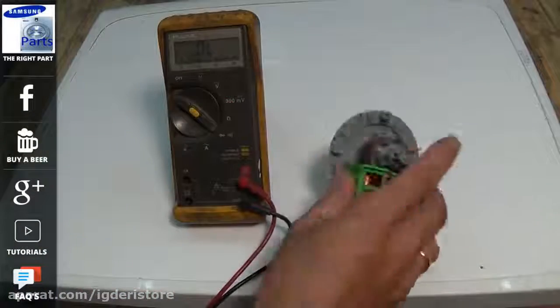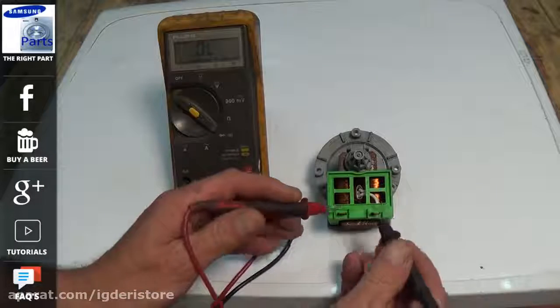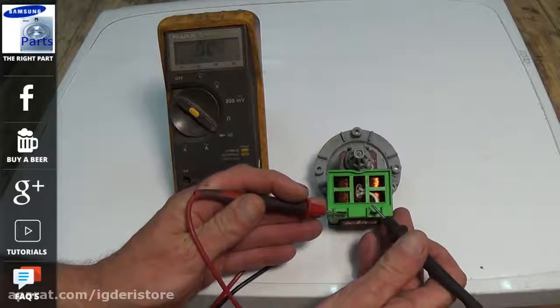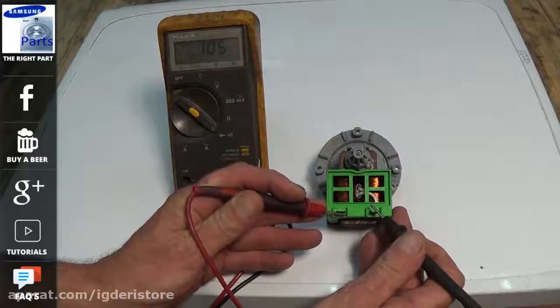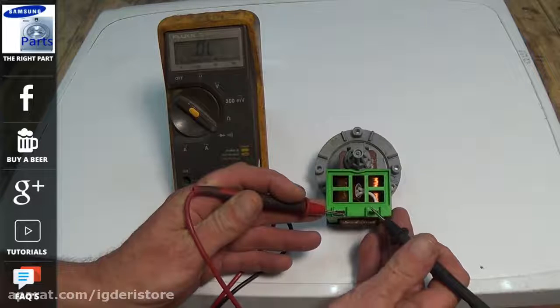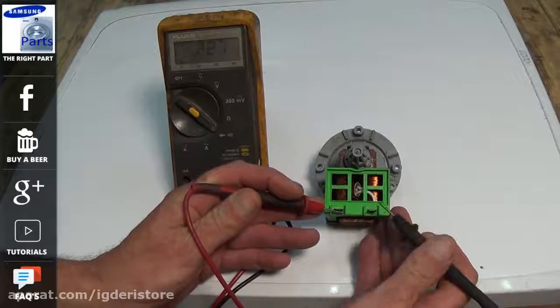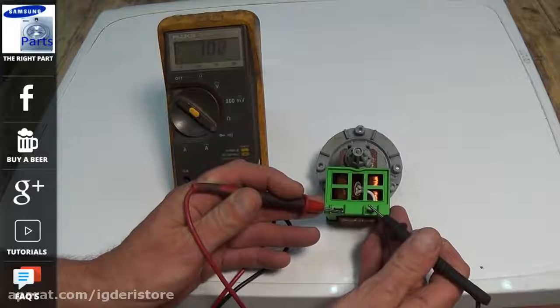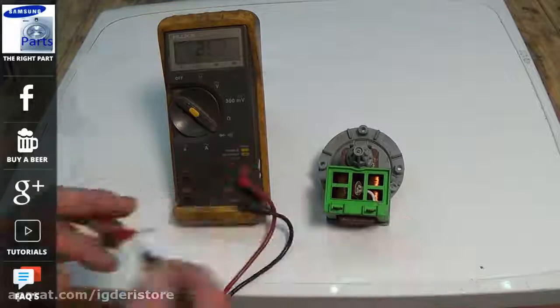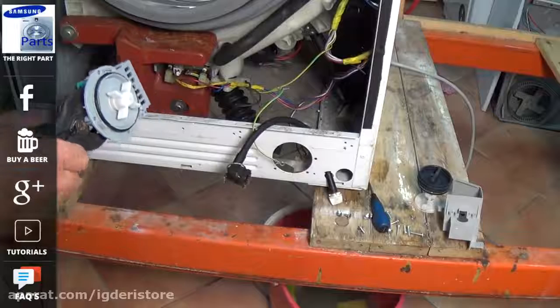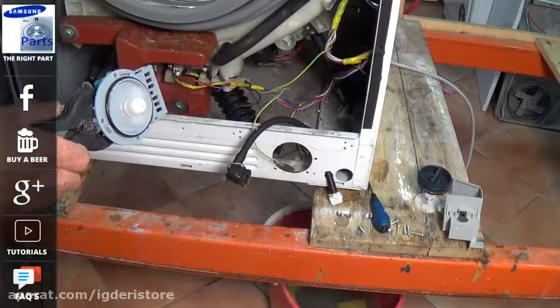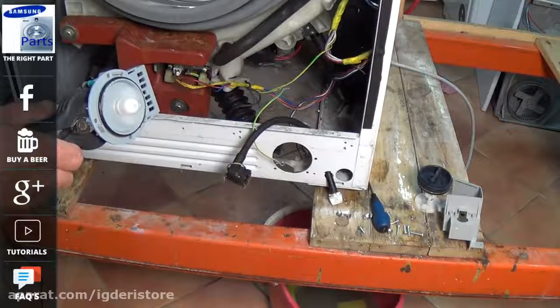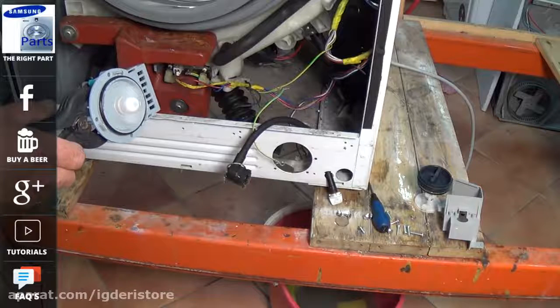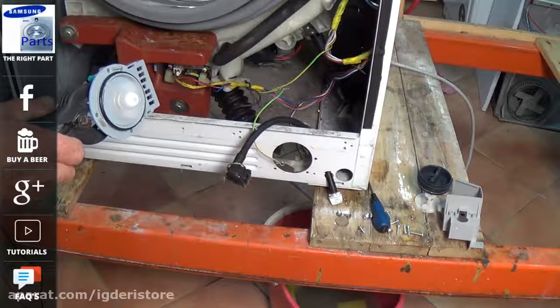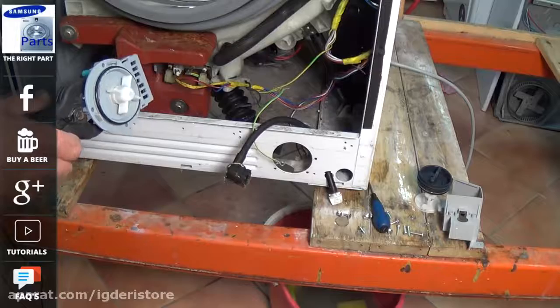Now the pump can only really be tested with a continuity test. It is not earthed, so we know the windings are good, but this doesn't always mean that the pump is actually in good condition. The windings can be weak, and the pump can really only be tested under load. I'm just doing a simple bench test by connecting the pump directly to the electrics if it is a 240 pump.